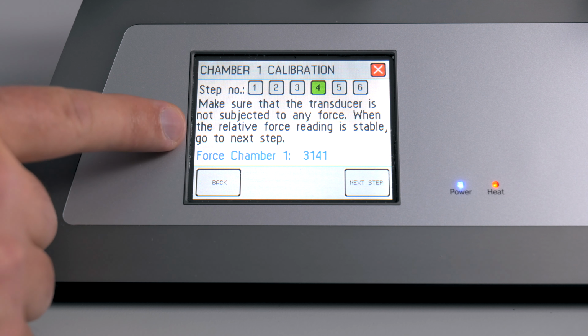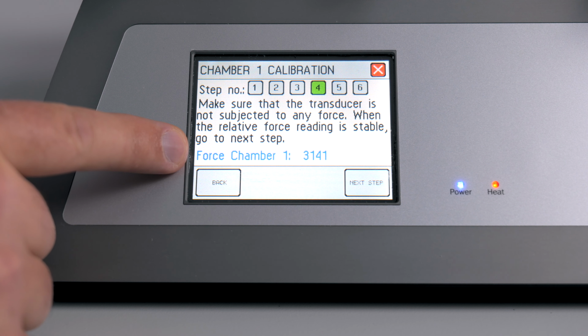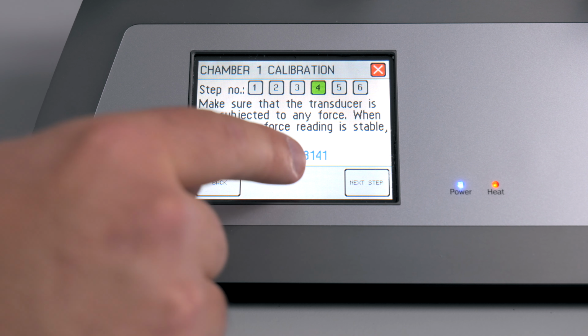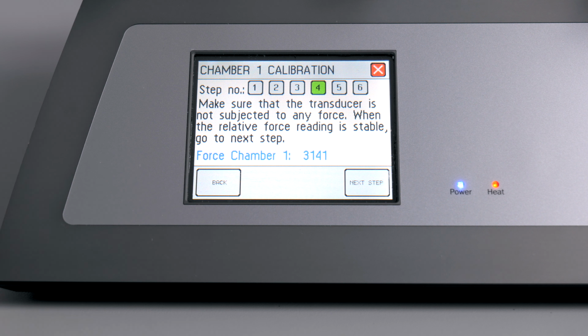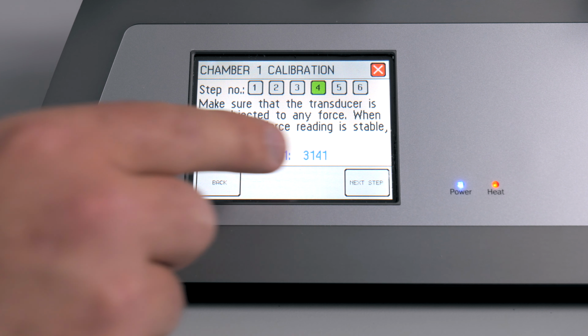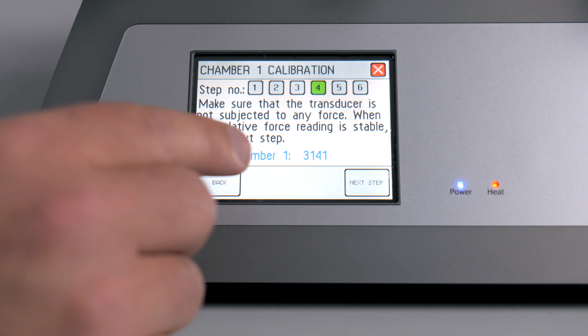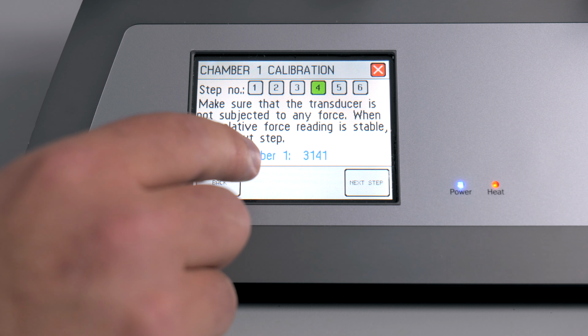Step 4 asks you to make sure that your force transducer is not subjected to any force and is giving a stable reading. If you see this number going back and forth between two numbers, that's all right. You just do not want it drifting in one direction. There's a good chance the T-balance is resting on the pin if this is drifting. If this is giving a stable reading, select Next Step.